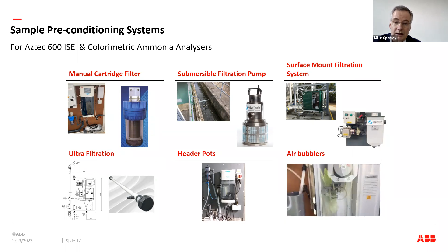What you find on the clean water side, you don't normally need filtration, maybe a manual filtration. But when we get into what I call the wastewater side, sample presentation is key here, and that's to allow for longer levels of maintenance. What we find in the UK, certainly within the water companies, they're doing a lot of demanning sites. Everything's being run like a factory farm. Managers, process people are into remote diagnostics. So therefore, they will only go out on a failure.